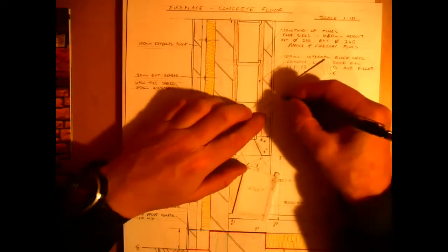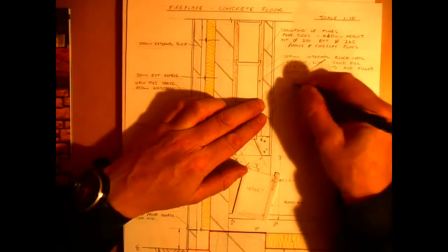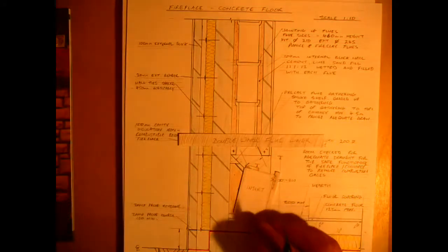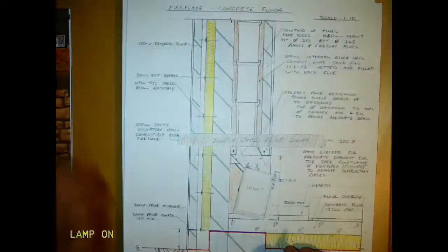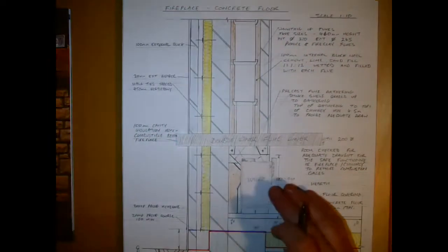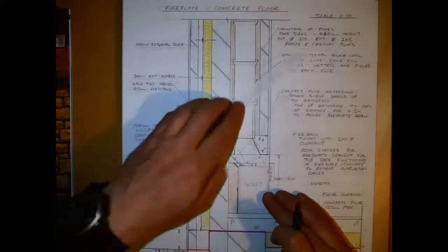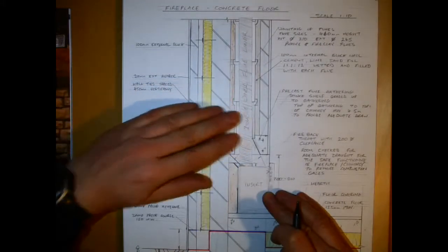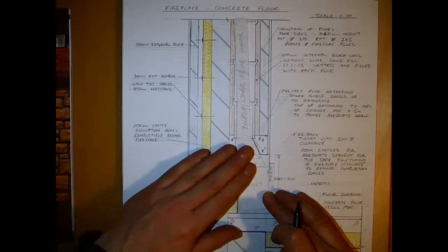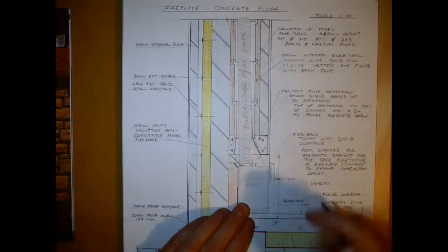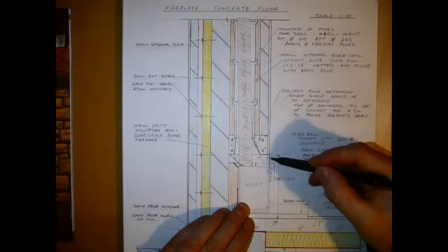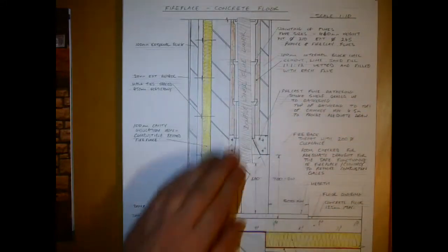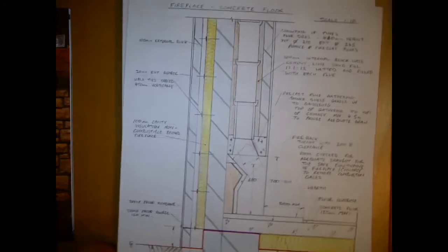But the insert itself, you can see it has plenty of room to fit into an open fireplace. Obviously without the fire back, there's no need for the fire back anymore, so the insert could be placed in there. And if it's wet, it needs a bit more space to get access to pipework, so across the width and the height you would have to have room for getting in for those connections to be made. And you can see the heat transfer wouldn't be as great when you have that space at the back of the stove, so you probably would get away with a 100mm block wall, or internal block wall in that.